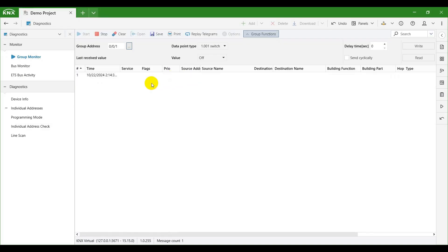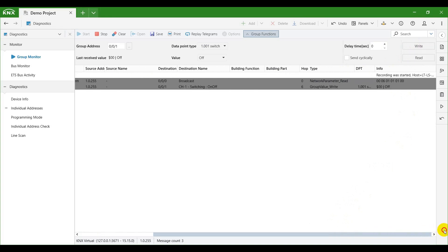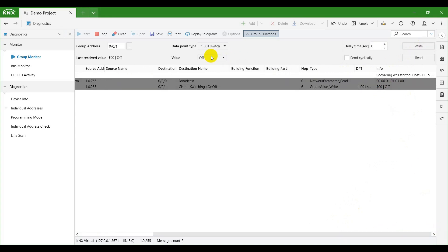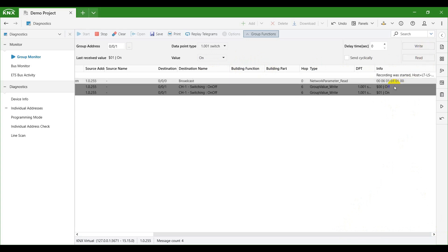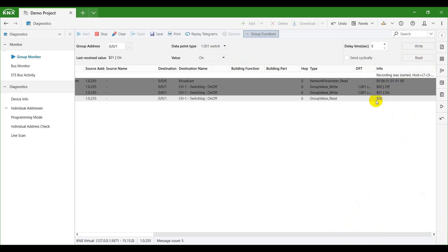We will first write the off value to group address 001 by sending a group value write telegram. You can see it recorded on the group monitor. Then we can write the on value and watch it recorded again.